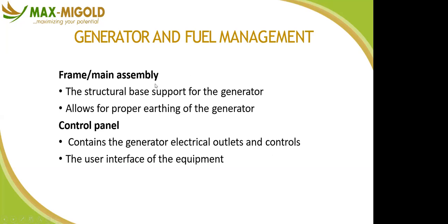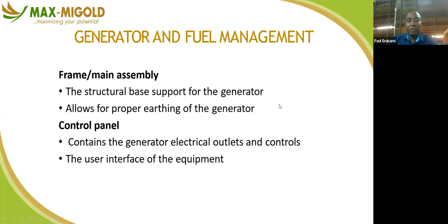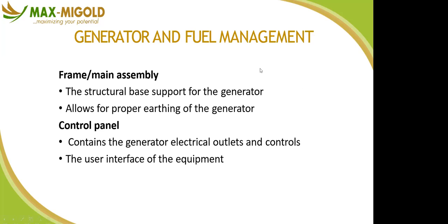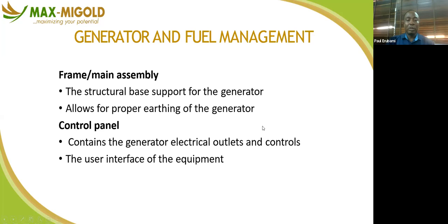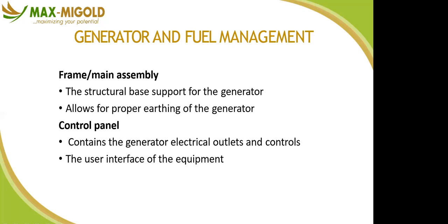So this is the frame. What it does is support the generator. Instead of vibrating, it helps to absorb the vibration. And also, it's a platform where you can do the earthing of the generator body. We have the control panel. That's where you communicate with the generator, the human interface between the generator and the human being, just like your computer. That's where you input anything you want the generator to do. So if you want it to start, start through the panel. If you want it to go off, switch off through the panel.